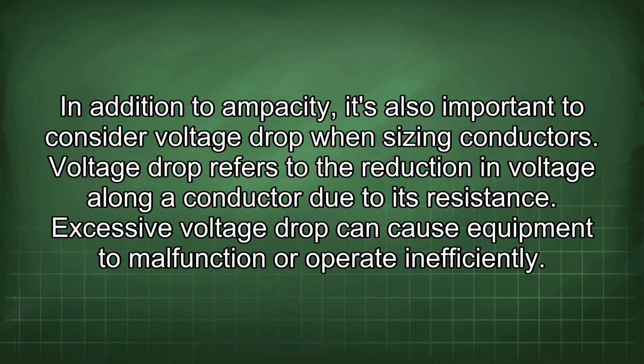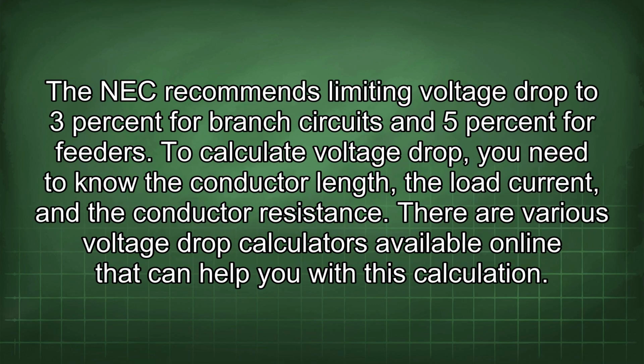In addition to ampacity, it's also important to consider voltage drop when sizing conductors. Voltage drop refers to the reduction in voltage along a conductor due to its resistance. Excessive voltage drop can cause equipment to malfunction or operate inefficiently. The NEC recommends limiting voltage drop to 3% for branch circuits and 5% for feeders.